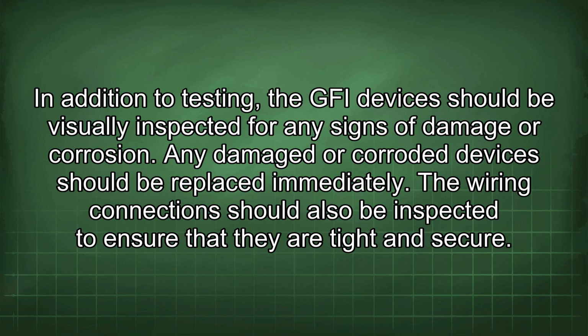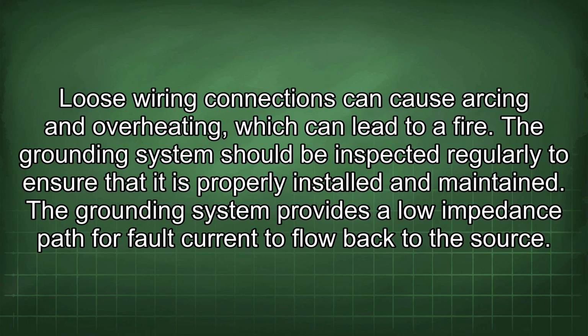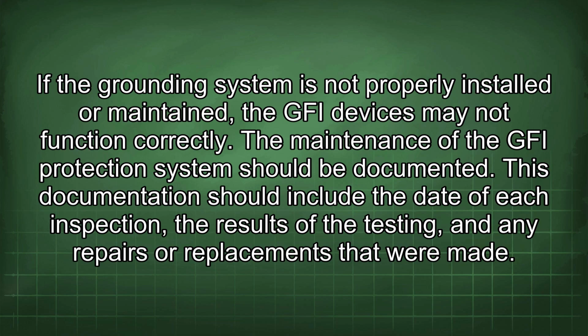In addition to testing, the GFI devices should be visually inspected for any signs of damage or corrosion. Any damaged or corroded devices should be replaced immediately. The wiring connections should also be inspected to ensure that they are tight and secure. Loose wiring connections can cause arcing and overheating, which can lead to a fire. The grounding system should be inspected regularly to ensure that it is properly installed and maintained. The grounding system provides a low impedance path for fault current to flow back to the source. If the grounding system is not properly installed or maintained, the GFI devices may not function correctly. The maintenance of the GFI protection system should be documented.